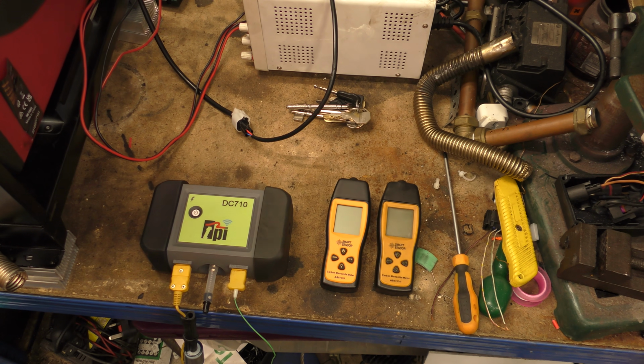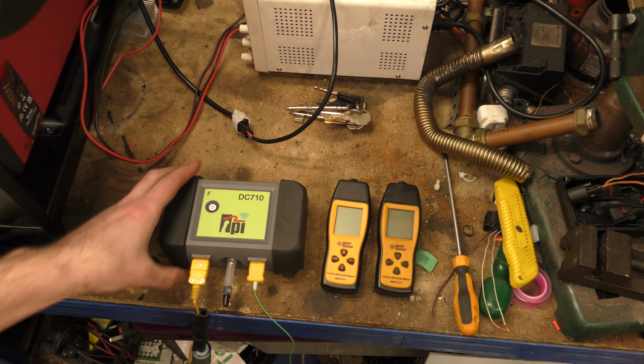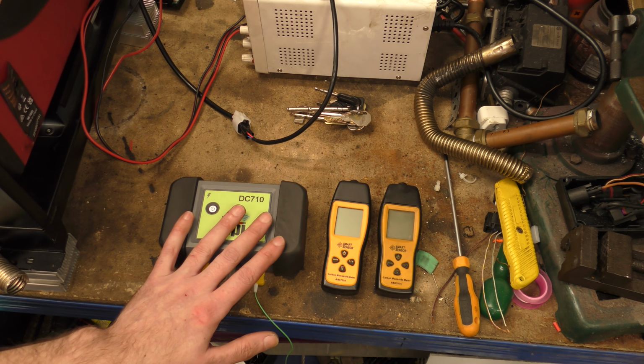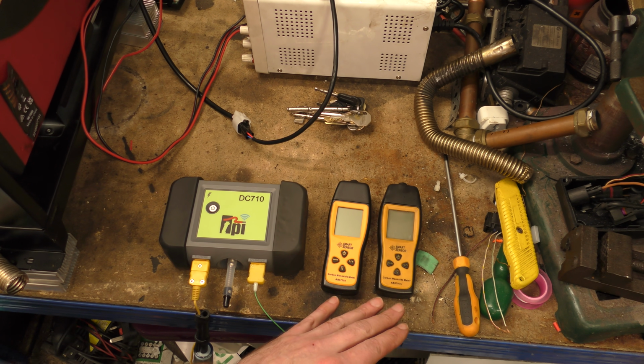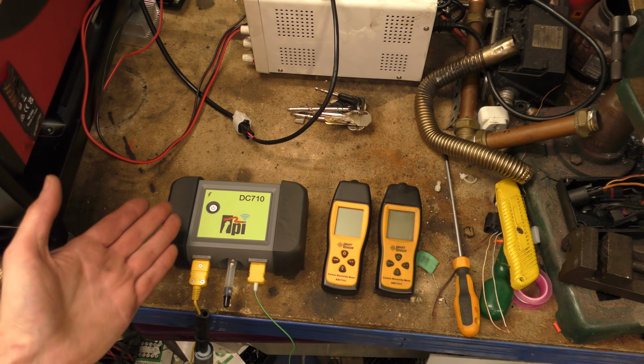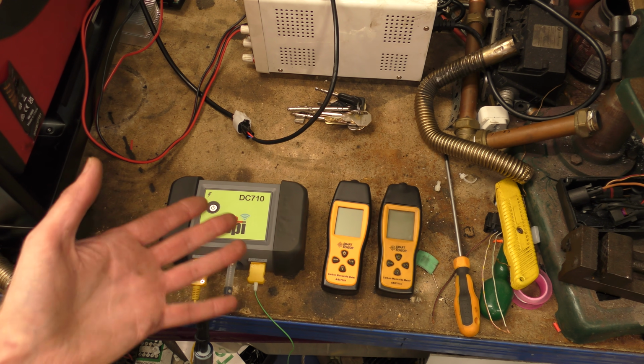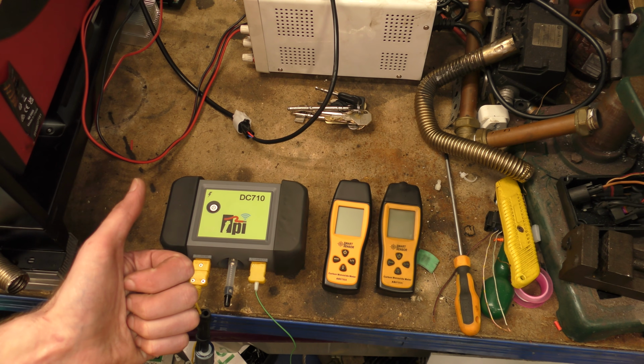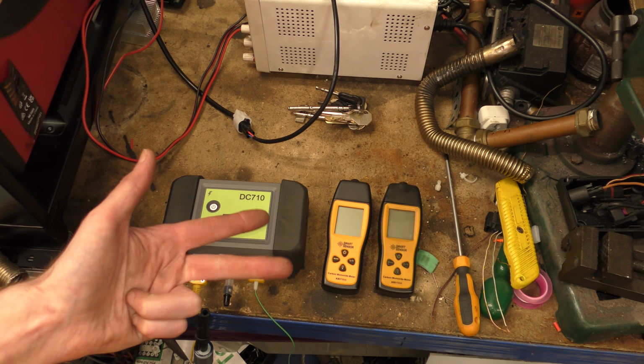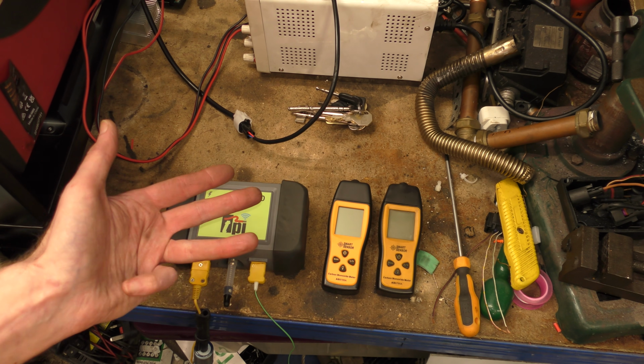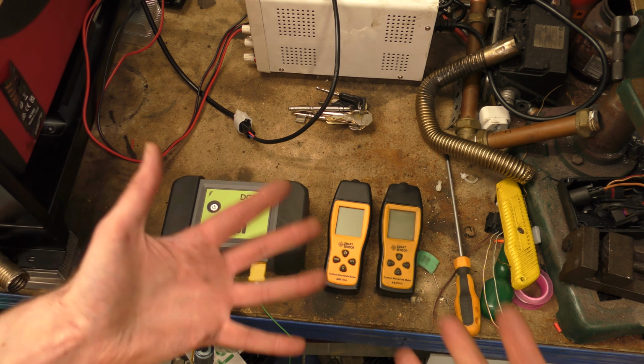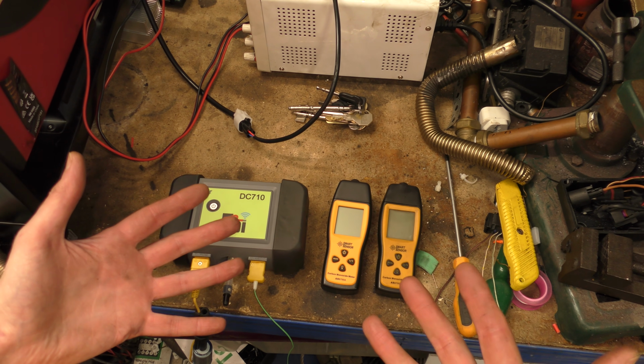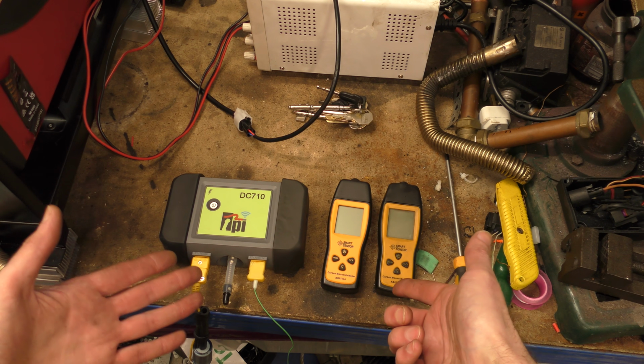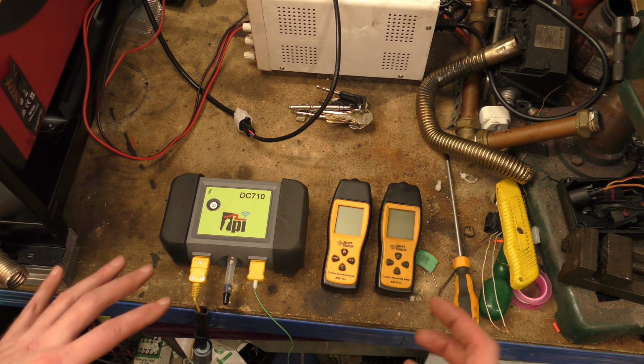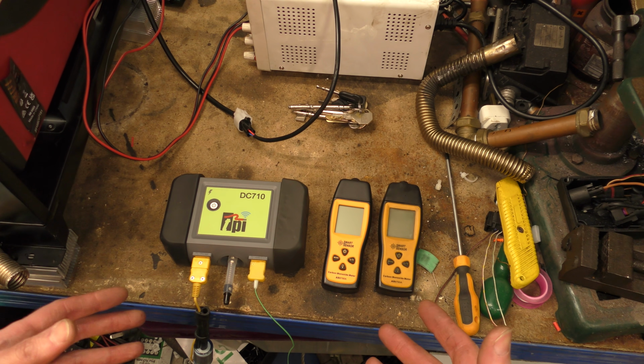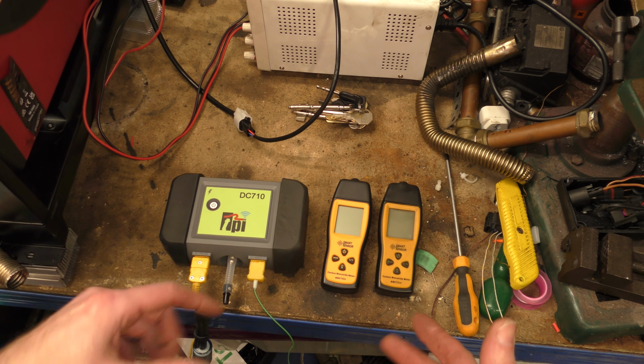What do I want to say about the comparison between using a combustion gas analyzer and the cheap carbon monoxide meters? On the expensive combustion analyzer, you've got a lot more data to play with - carbon monoxide, carbon dioxide, excess air, exhaust temperature and housing temperature, all on display at the same time. Whereas with the carbon monoxide meter, you're just getting a rough reading of carbon monoxide mixed with outside oxygen as it leaves the exhaust.